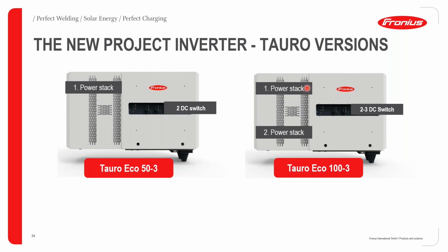Looking at the 100 kilowatt version, you still have the power stack. If you look at the 50 kilowatt, we have one power stack, and the 100 kilowatt is coming with two power stacks. That gives the advantage that if one power stack has an issue, then the inverter can continue to perform at half the capacity. In terms of DC disconnection, we are talking about 2 to 3 DC switches for the 100 kilowatt version.